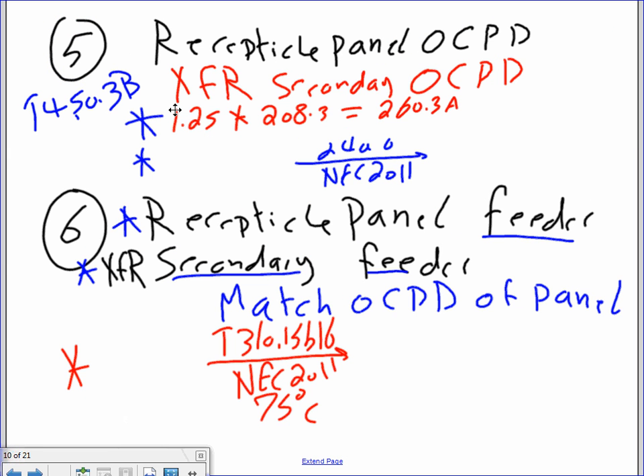260.3, okay? Then you're going to take the 260.3 amp to the walls. Do we have 275 or do we have to go to 300? 300. We don't have 275. So my next standard, guys, from 240.6 is 300. Same, match the overcurrent protection device. We have 250. We don't have 275. So you go next to the next standard, which is 300. So up, 300 amps.